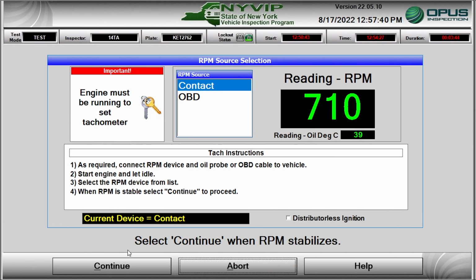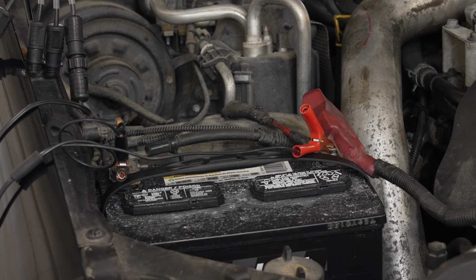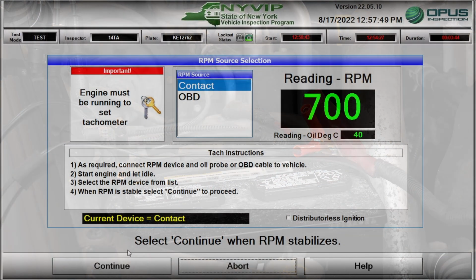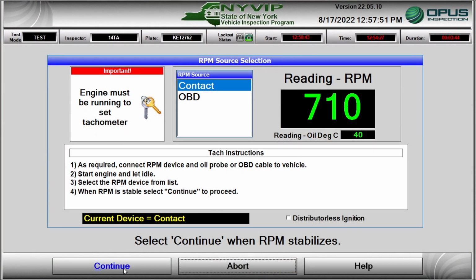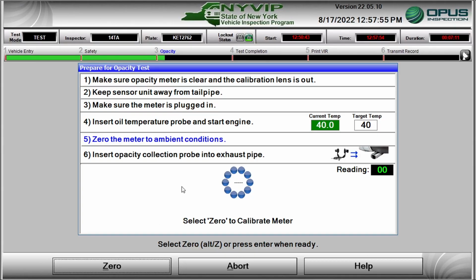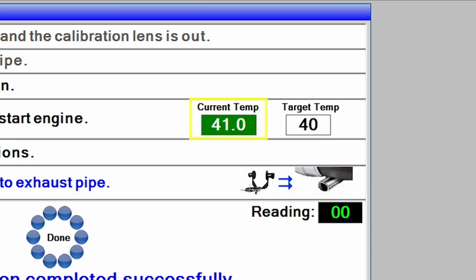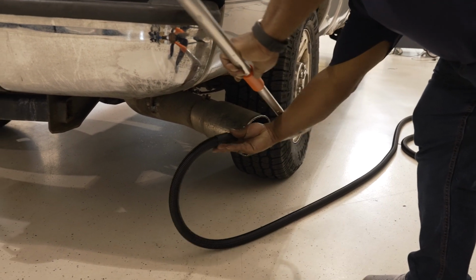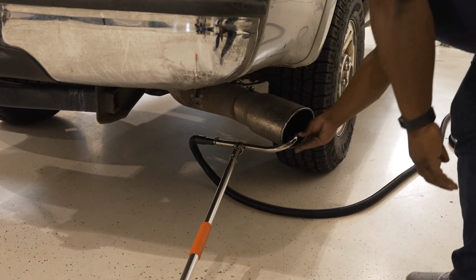and observe the RPM readings for stability. In most cases, the battery sensor works better than the vibration sensors. When stable RPM readings are being observed, click the Continue button to return to the Prepare for Opacity screens. Click on the Zero button to zero calibrate the opacity meter. Observe the oil temperature. A minimum reading of 40 degrees Celsius is required to continue testing. Place the heated exhaust sample probe tip in the tailpipe.